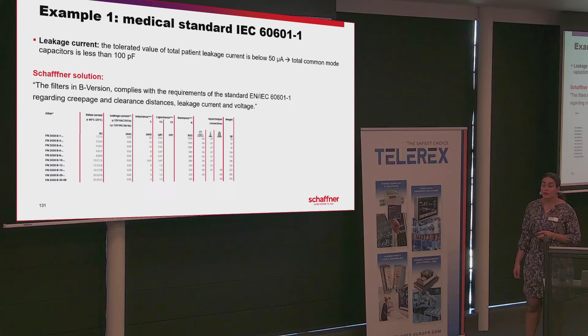And unfortunately, if we respect this requirement, we definitely affect the performance of the filter. So here we have the same filter with and without the common mode capacitors. And as you can see, we severely impact the performance of the filter. This is the filter attenuation. So we severely impact it by removing the capacitors. So in order to solve this issue, what we can do is to add an earth choke to our filter.